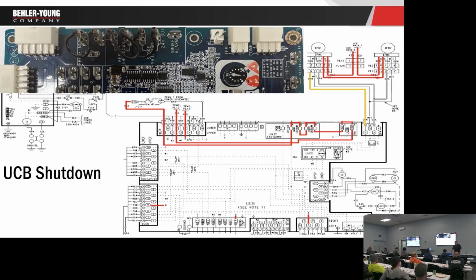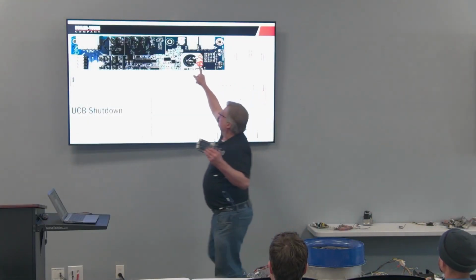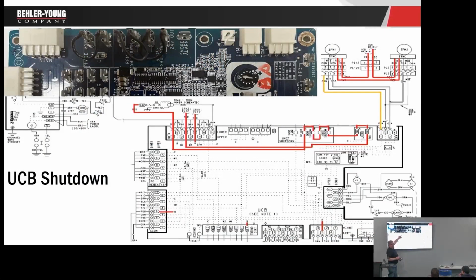So if I have to take this board and lay it on its side like this, okay? So you can see here, here's my board laying on its side. This plug right here is this right here. So this number 1 terminal right here, if I follow it back, it's coming from the transformer. Everybody see that? Now I will say something. As many years as I've been in this field, I hate their wiring diagrams. I'm not gonna lie. I really, really do. I really hate them. But in 20 years working for BY, I still hate them. But so if I follow this, see the red wire, so off my transformer, does it go anywhere else? No, it goes right here first. Nowhere else in the unit. And it comes right to here, and I have my 3 jumpers. My jumpers for my smoke detectors right here.